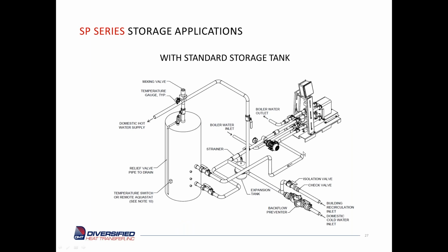And we talked about the storage. We feel that anytime we're working with commercial laundries or commercial kitchens that have high capacity machines in them, we need to have some water up front in storage. So we recommend putting several hundred gallons of water in front of these commercial type laundry machines and dishwashing machines. It's just a much better design, and it keeps these large dump loads from affecting the performance of the unit, especially if it's tied in with other parts of the building. So we want to have that type of storage in front of the unit.